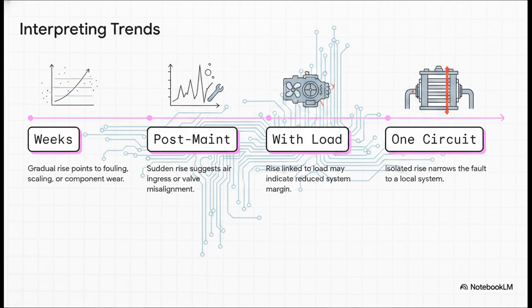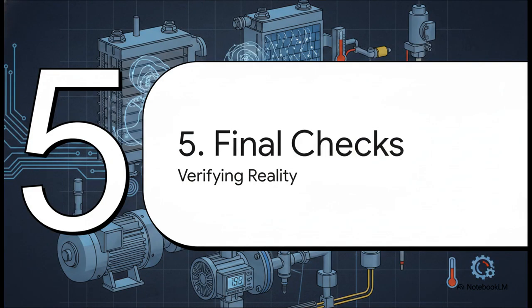A sudden spike immediately after maintenance? I'd bet money on air in the system or a valve that wasn't put back to its proper position. If the temperature only gets high when you're at full sea speed, but it's stable at lower loads, then your system's overall cooling margin is probably getting smaller. The trend tells you where to look. So now we're at our final checks.